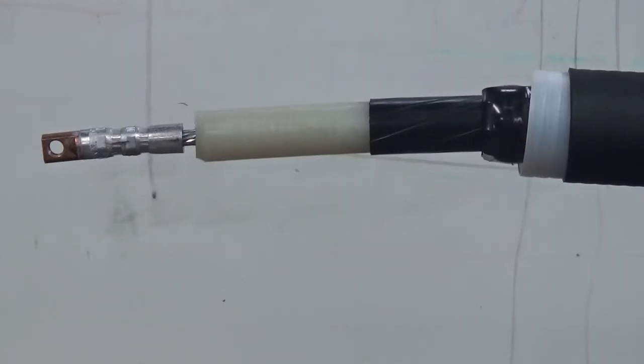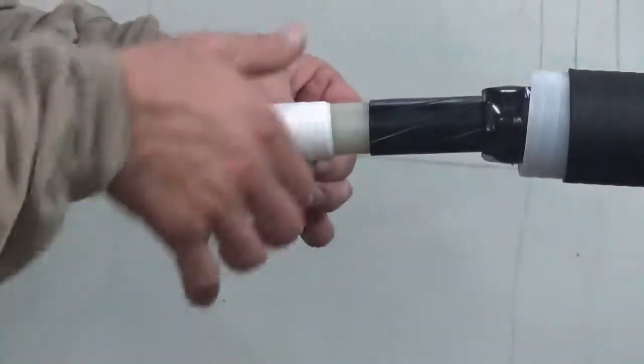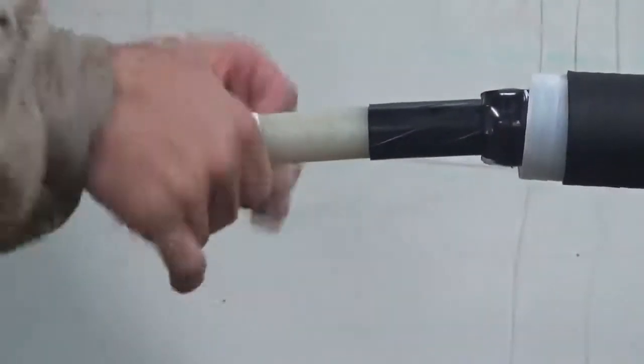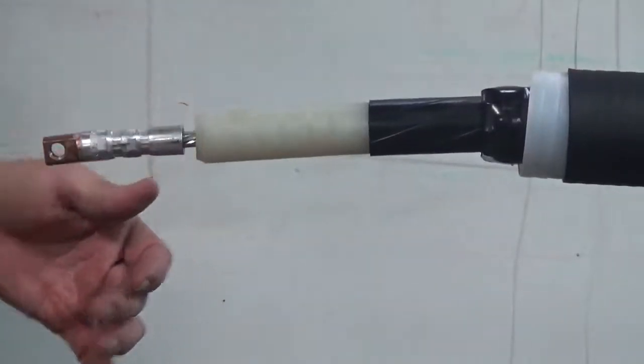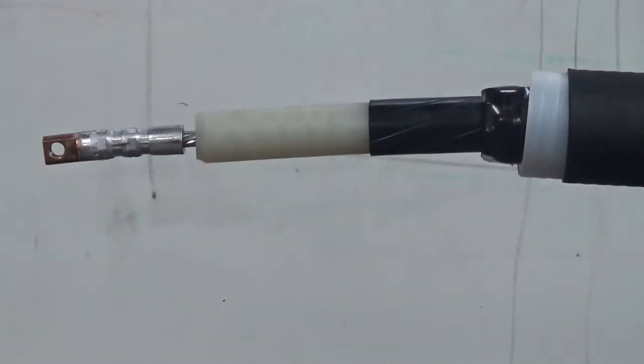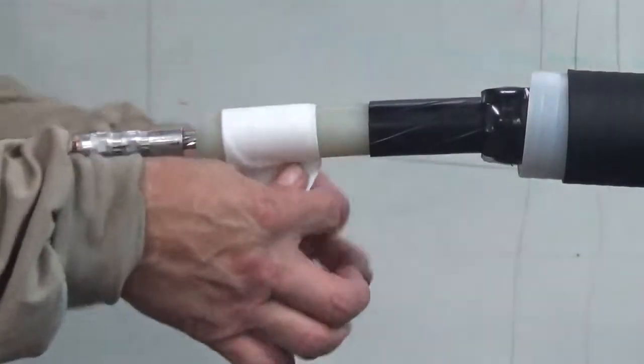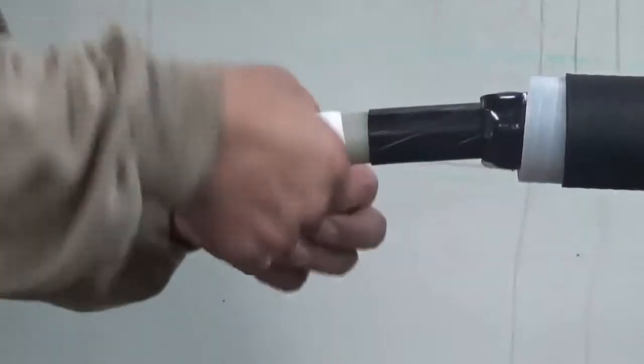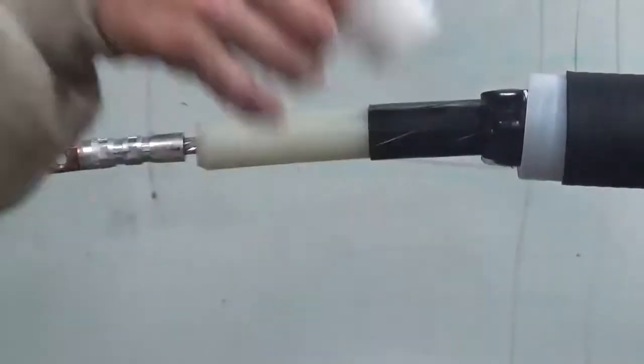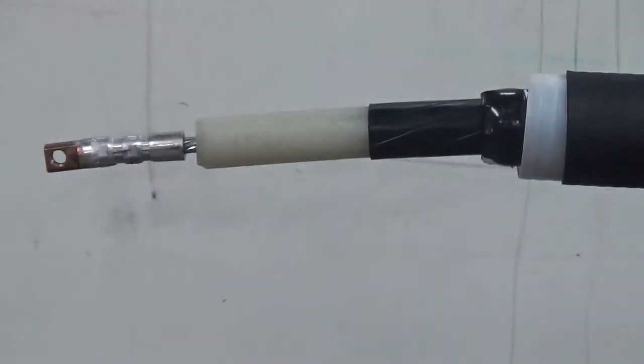So now we'll cable clean it real good, taking care not to touch the semicon with the cable clean. Just wrap it on there, make some good twists all the way down to the lug, then take one and go the other way a little bit. Again, you don't want to really put the cable clean on the semicon hardly — you want to just kind of get it there and then clean it off. See how he did right here.